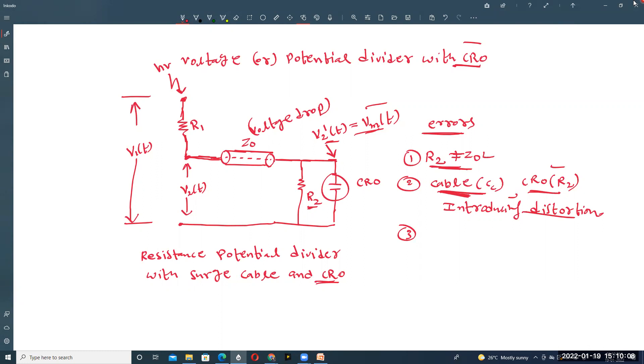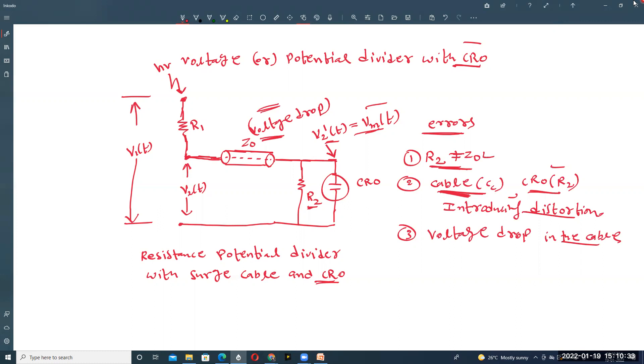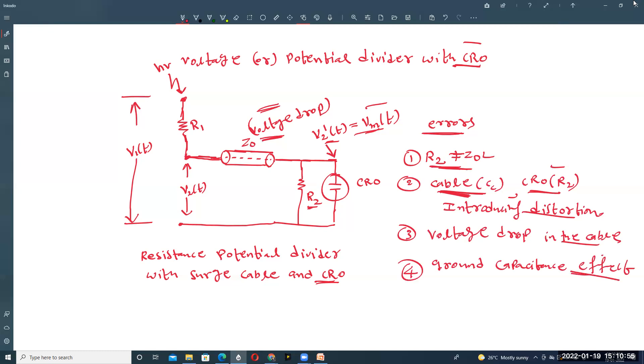There is also an error present in the resistance potential divider with surge cable and CRO. The third error is voltage drop in the cable. Because of this voltage drop in the cable, there is an error in the measurement of voltage. The fourth error is the ground capacitance effect, which also introduces errors in the measurement of high voltage using a potential divider with CRO.